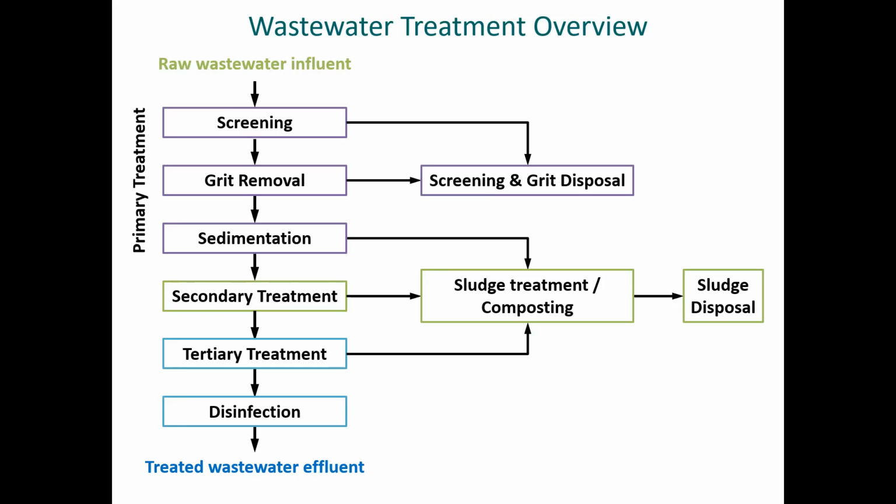Secondary treatment is mostly biological, where we're adding oxygen and trying to get microorganisms to eat all the organics and phosphates and nitrates that are in the water, and then eventually they're going to settle out. There are anaerobic processes too sometimes. And tertiary treatment, we talked about a little bit, which includes things like UV and ultrafiltration.